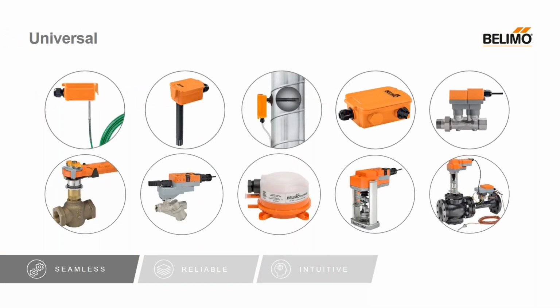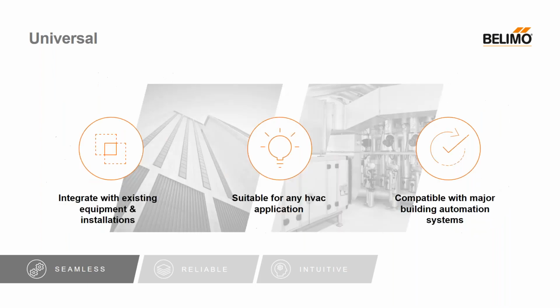So much like our valves and actuators, everything we make is universal and it's designed to work with anybody's control system. So standard outputs from the devices: 10K type 2, 10K type 3, 20K NTC, 0 to 10, 5 to 10, 4 to 20 milliamps. You know, everything is universal. It's no different than any other input, or there's no specifics to the outputs from the sensing devices that you would have to have some unique input configuration at your controller. So everything's standard. It's really designed for the HVAC industry.